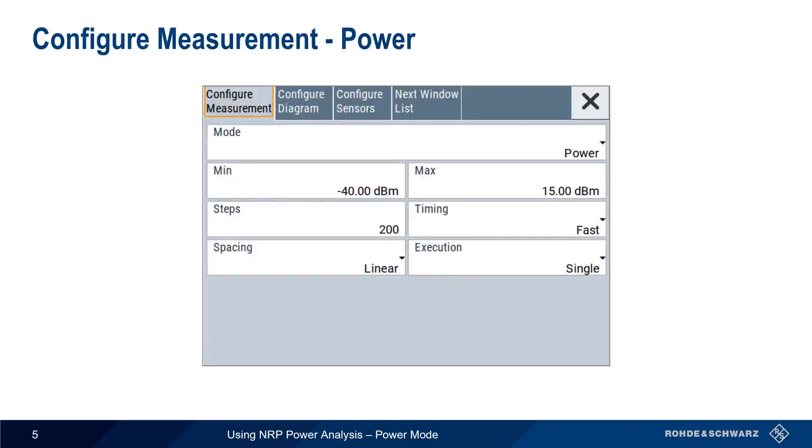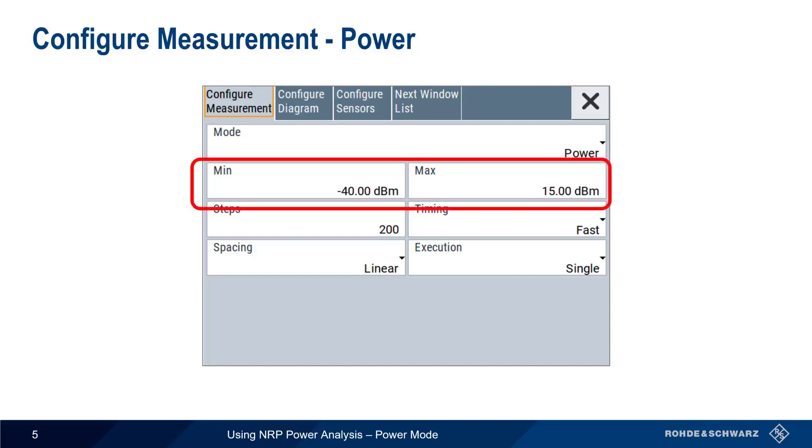Just as in frequency mode, we have to enter our measurement limits, but this time in terms of min and max powers. Here, minus 40 dBm and plus 15 dBm. These should be carefully chosen based on the DUT parameters.